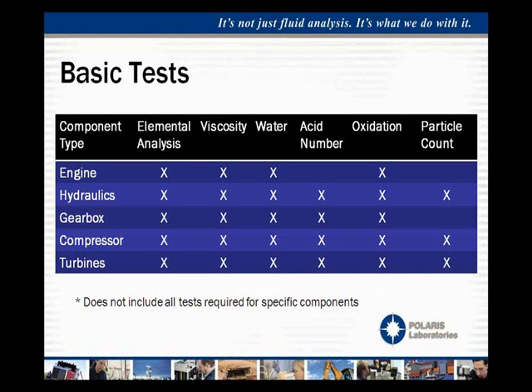With an engine, we're going to do basically elemental analysis, viscosity, water, and oxidation tests. With hydraulics, because of their particular application, they require a couple different tests because of their performance requirements. With hydraulics, we add on a particle count, which tells us how clean that fluid is. Hydraulics typically have clearances that are a lot tighter than an engine, so they need fluid that is a lot cleaner just to maintain their integrity and functionality.